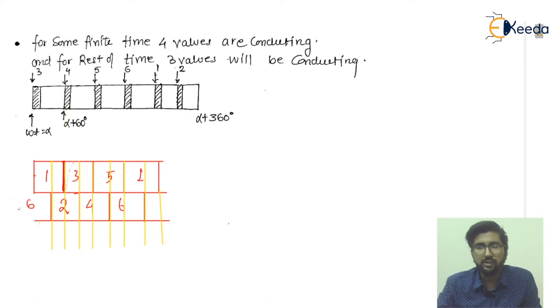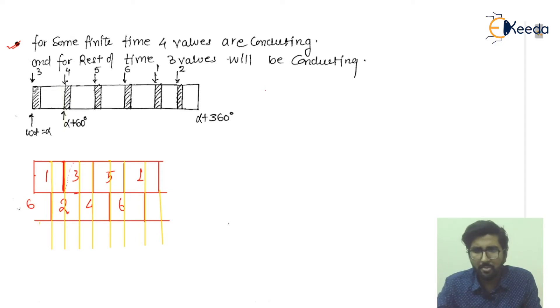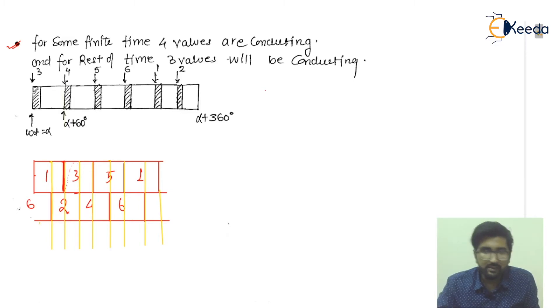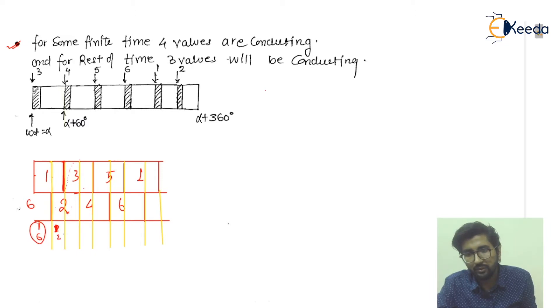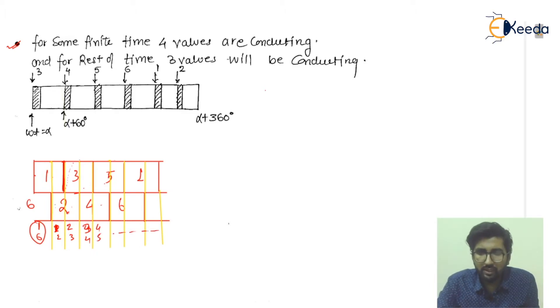Looking at the diagram: the upper portion shows thyristors 1, 3, and 5 (upper commutated group), and the lower portion shows thyristors 2, 4, and 6 (lower commutated group). In the ideal case, at any time one from each group conducts: first interval 1 and 6, second interval 1 and 2, third interval 2 and 3, fourth interval 3 and 4, then 4 and 5, and so on.